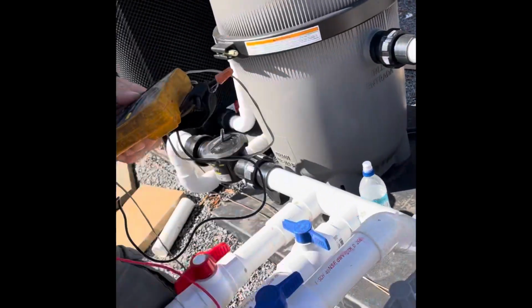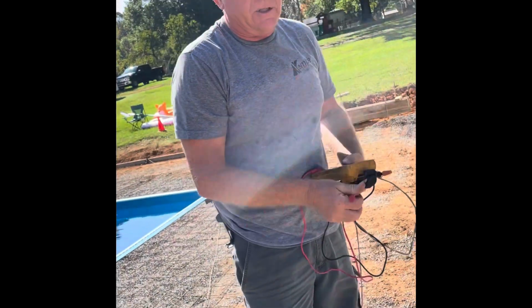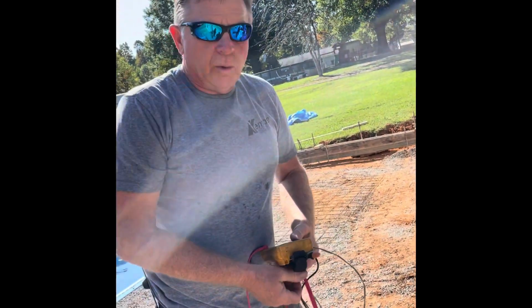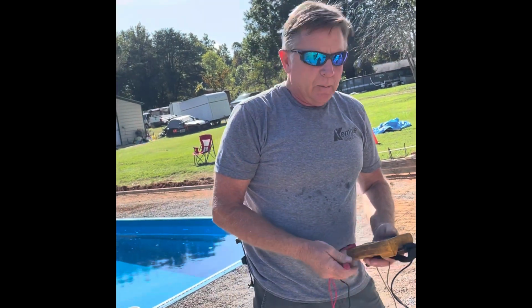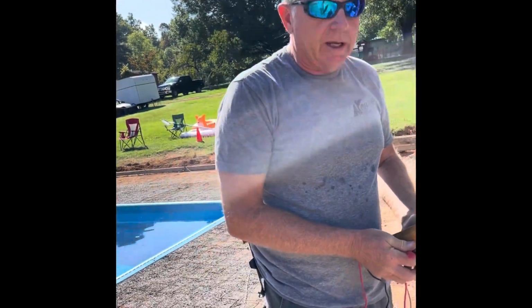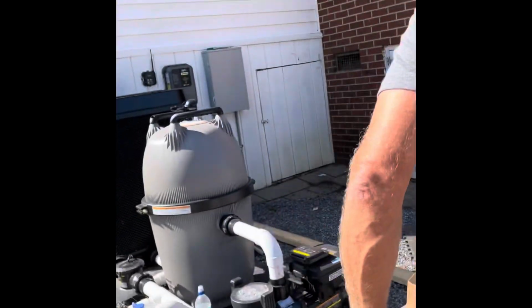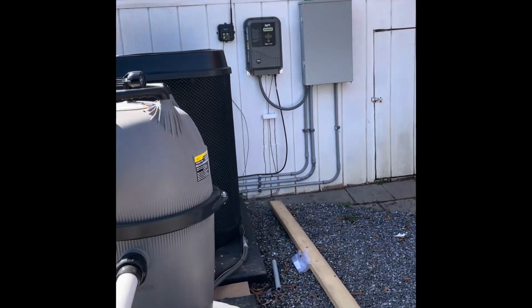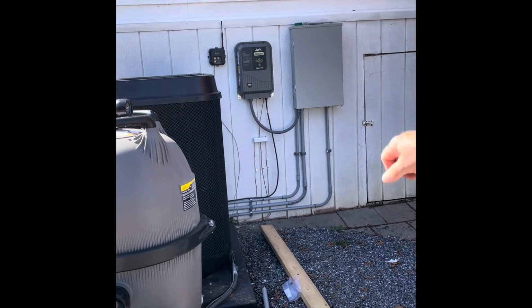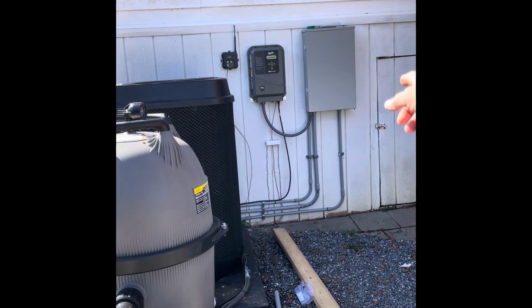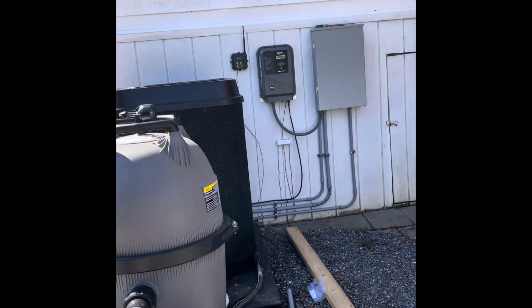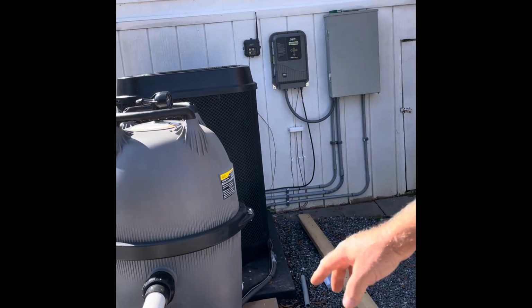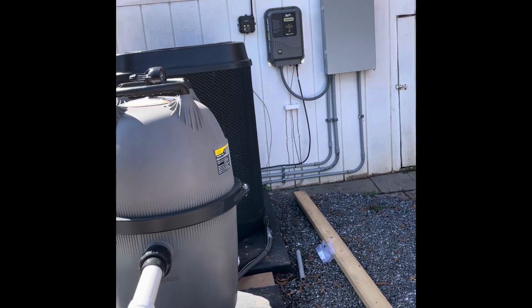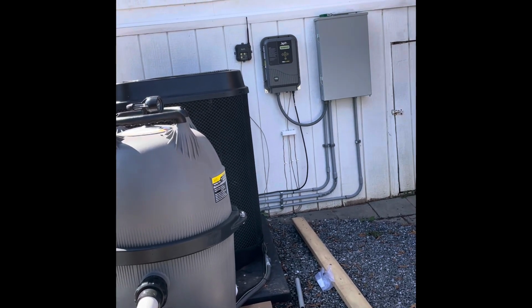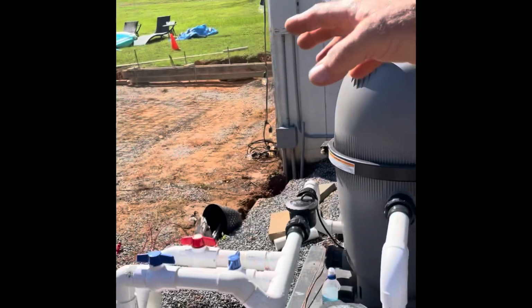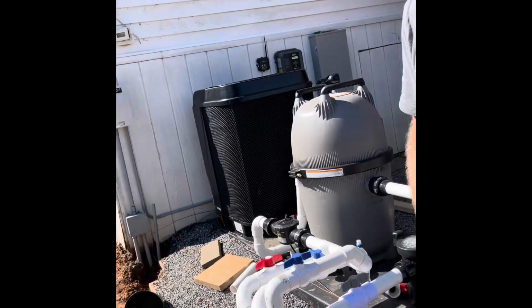We've tested a lot of pools and we just find this DC number to be significant. We're not engineers. We'd like any input from anybody that could help. What we've done is we've taken it upon ourselves to put a utility ground tap system in, so we're able to disconnect any parts of the system that we want to do any of our testing. We have one that goes to our water bonding device here underground. We have another one for the heater and the pump and the chlorination system. And then we have another third one there that is going out here to the metal mesh and will pick up the ladders.